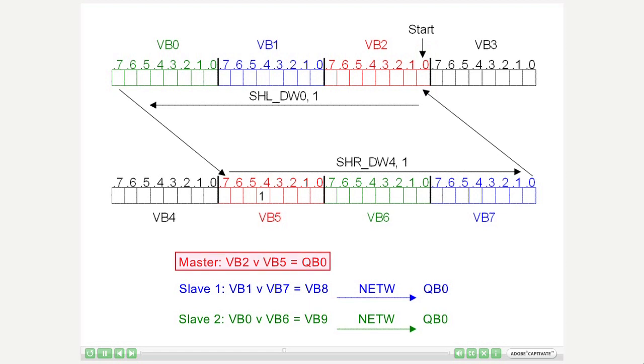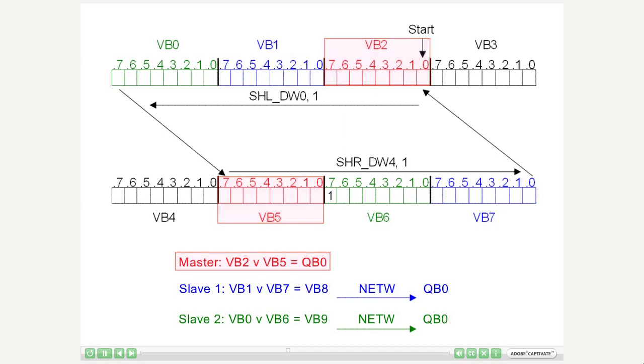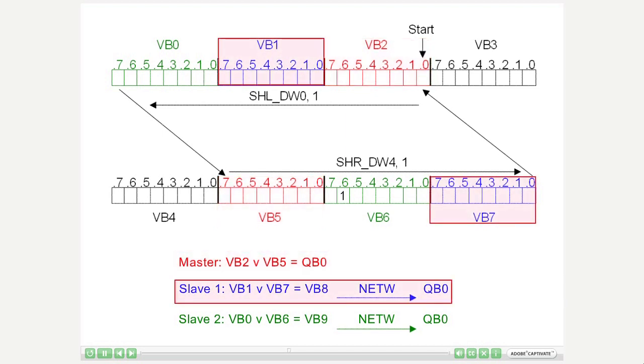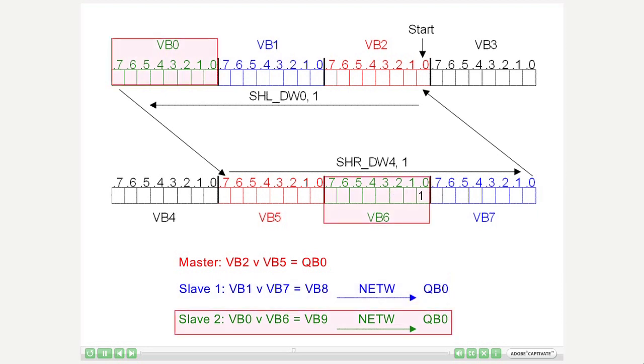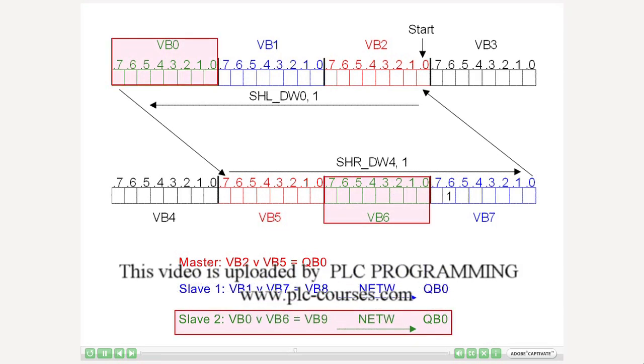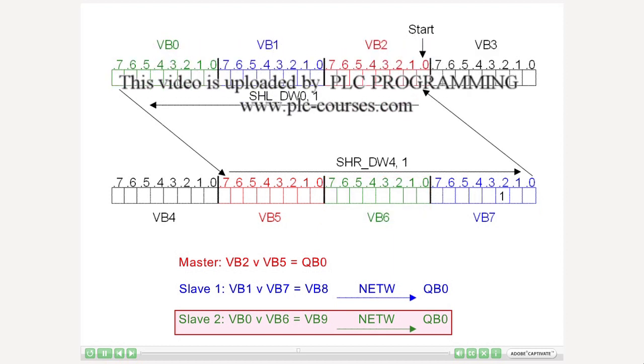Output byte 0 of the master results from the logic OR connection of byte 2 with byte 5. Byte 1 OR byte 7 results in byte 8, which is written to the output byte of slave 1 via NetW, and byte 0 OR byte 6 results in byte 9, which is written to the output byte of slave 2 via NetW.